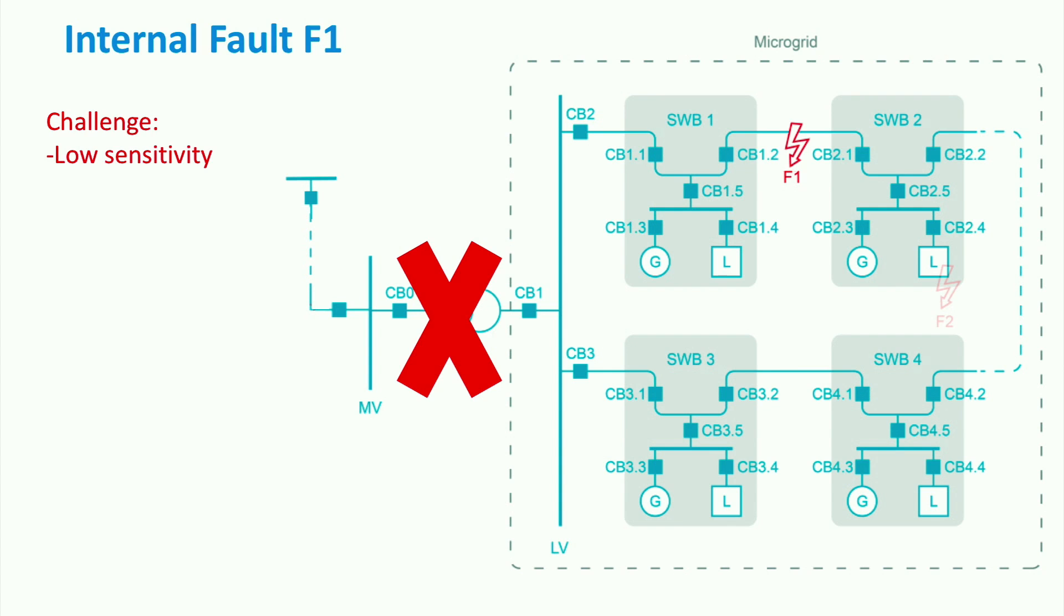There are two possible solutions to overcome the lack of sensitivity. As the microgrid has very low short-circuit currents, the first solution is to connect a new source, such as a diesel generator or flywheel, which can provide high fault currents. However, this might increase both investment and operation costs of the microgrid.